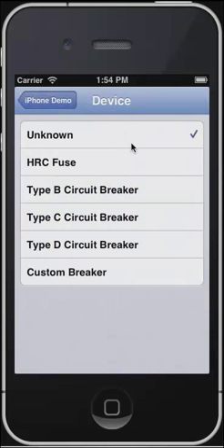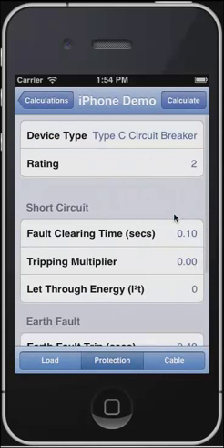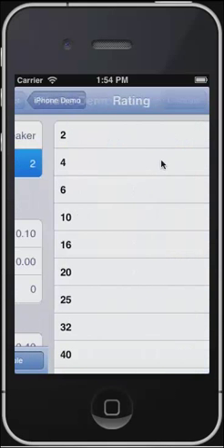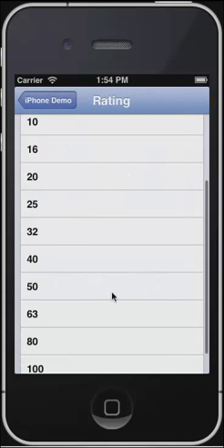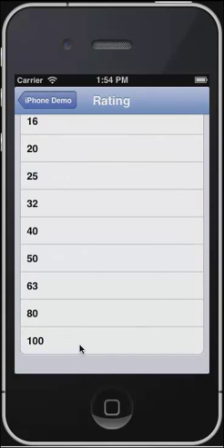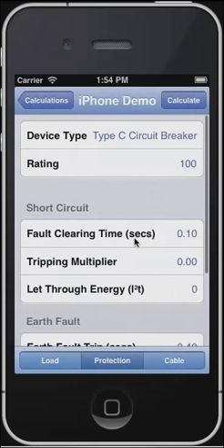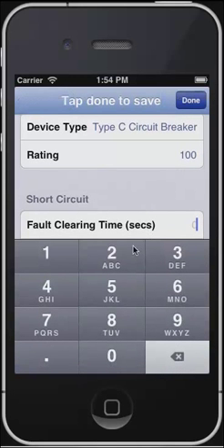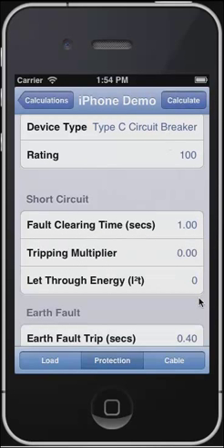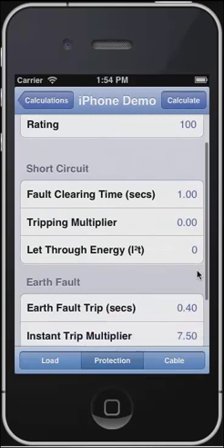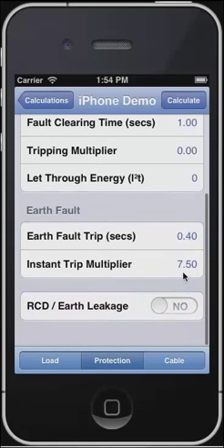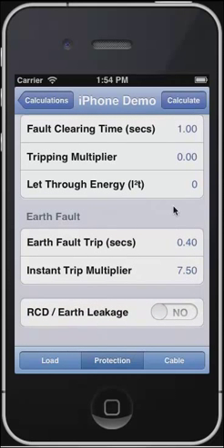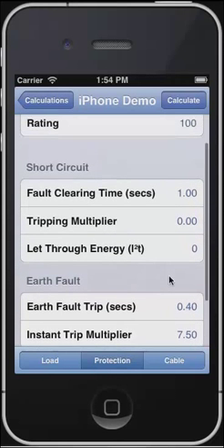Here we can enter our device type — we'll enter a type C breaker. We can then drop down the list and enter the rating of that breaker. We can also put in our short circuit clearing time details, our earth fault loop tripping, and whether we have an RCD or not.